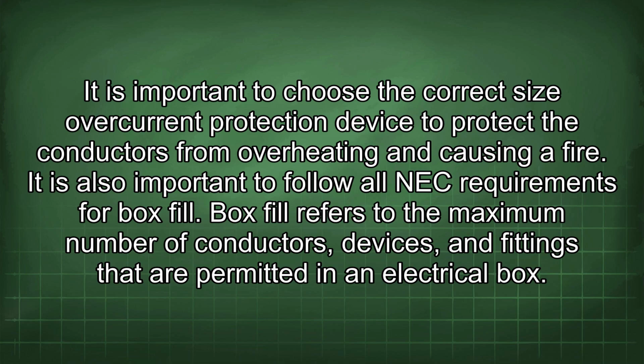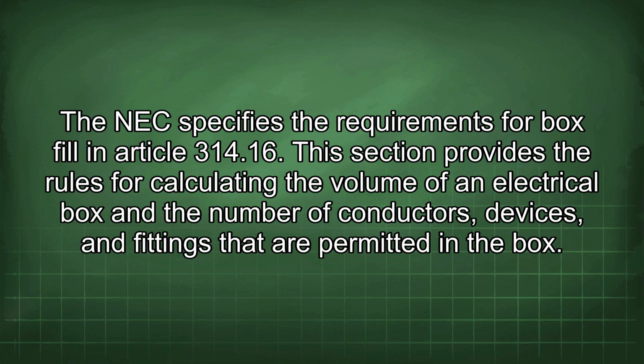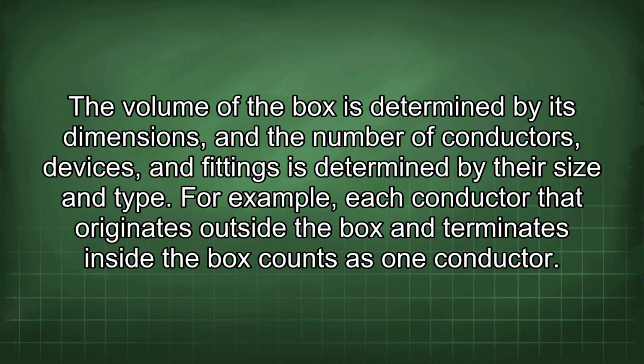Box fill refers to the maximum number of conductors, devices, and fittings that are permitted in an electrical box. The NEC specifies the requirements for box fill in Article 314.16. This section provides the rules for calculating the volume of an electrical box and the number of conductors, devices, and fittings that are permitted in the box. The volume of the box is determined by its dimensions, and the number of conductors, devices, and fittings is determined by their size and type.